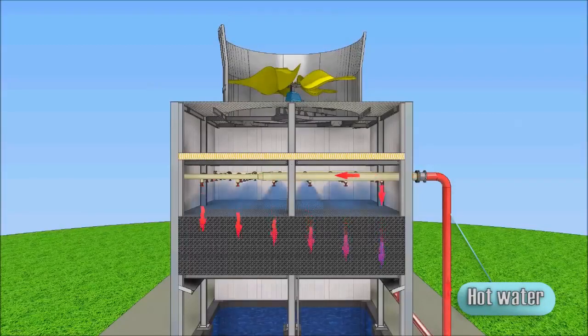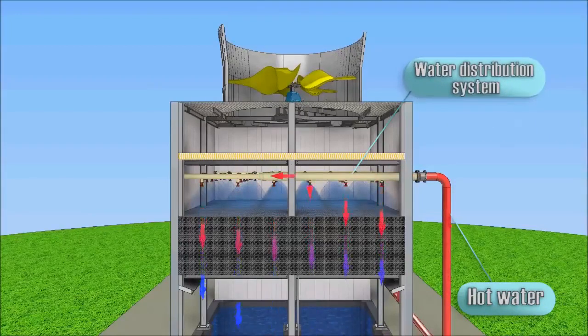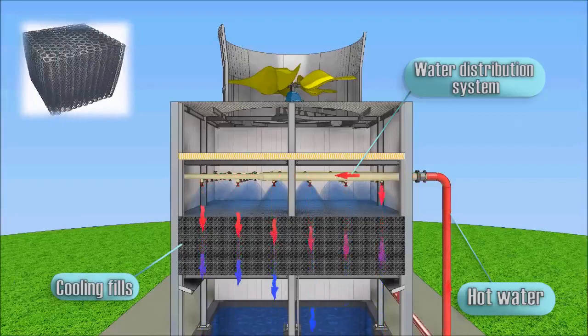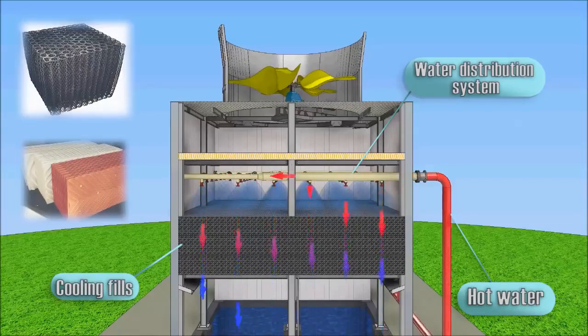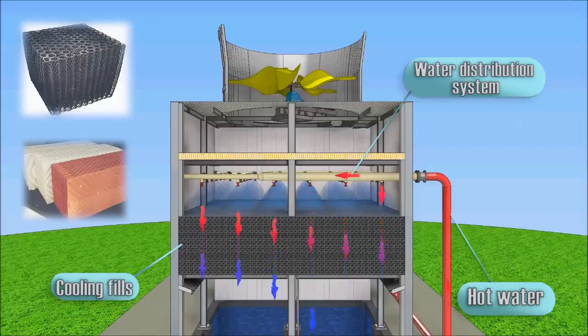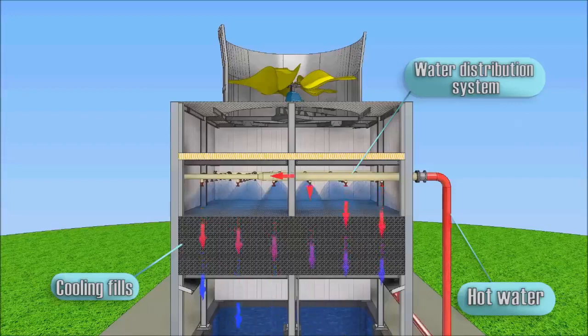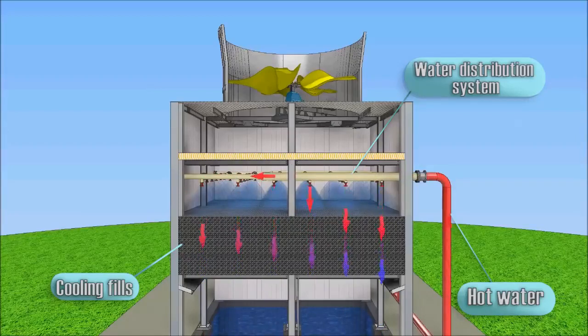Hot water from various sources such as machines or heating processes flows through pipes to the distribution system of the cooling tower, which produces even water distribution to all the area of fills by spray nozzles. On the fills, a water film is formed on the surface, from which evaporation occurs as it encounters the airflow. The larger the surface area of the fills, the more intensive the evaporation and the more efficient the cooling tower.